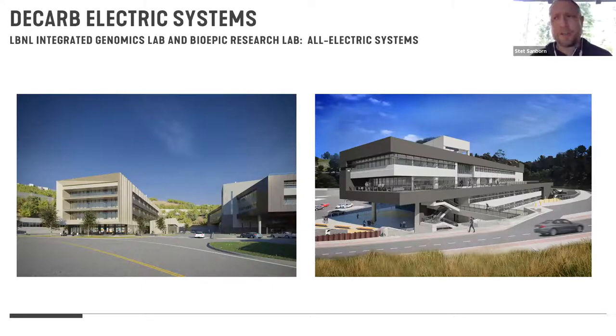A big effort though on these projects is actually utilizing the waste heat that's coming out of the exhaust hoods. You know, you're moving a lot of air through research labs, from 4 to 12 air changes, depending on the crazy stuff that they're doing in there. And so a key component to working on these complex projects is looking at that exhaust airstream as a quality source. It's of that level of quality as the sewage leaving a multifamily project. You know, you have beautiful 70 degree air leaving this project year round. Traditionally we've always used runaround coils. We've now moved to using six pipe water source heat pumps to do simultaneous heating and cooling using that exhaust airstream as our source, which is really fun.